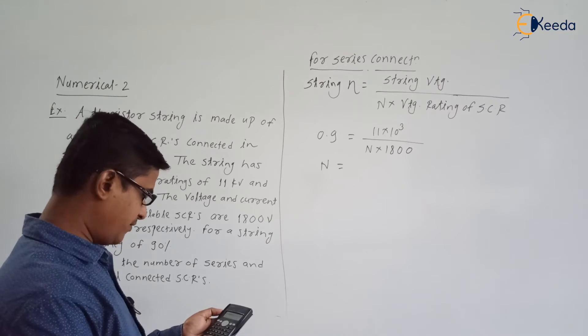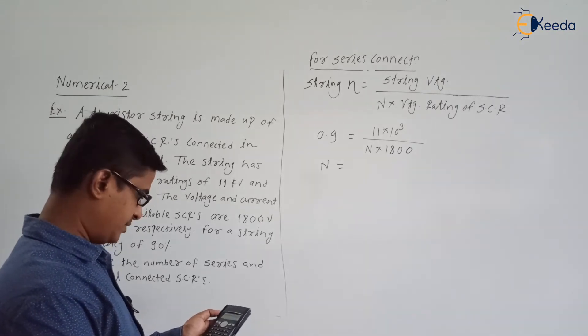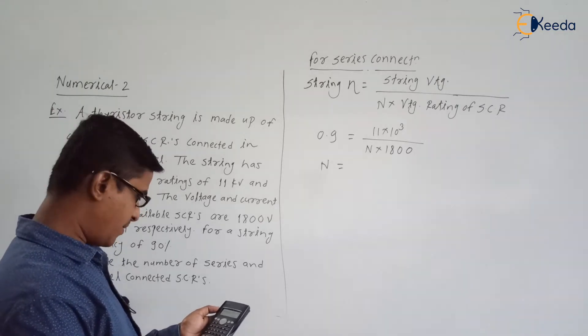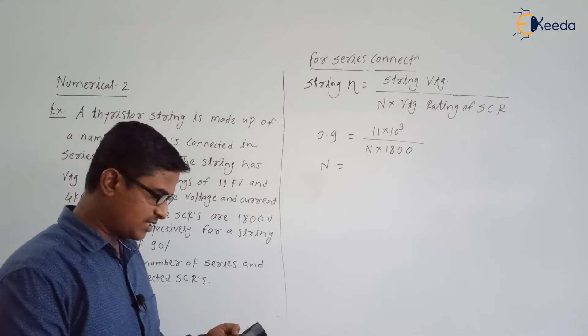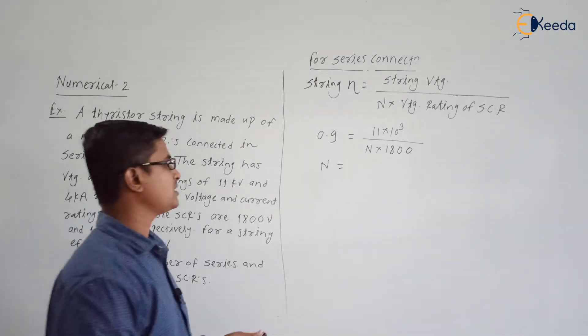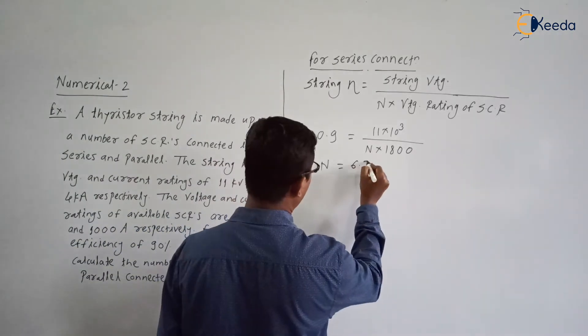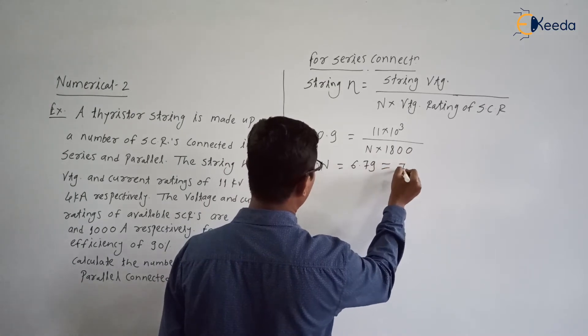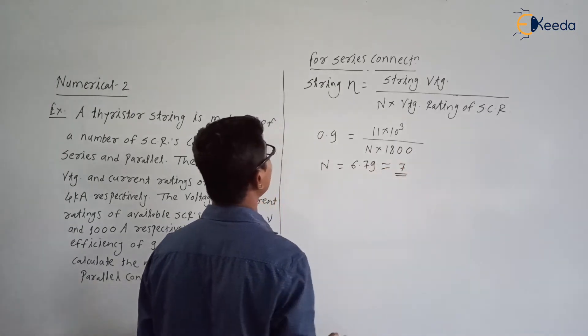So from this can we find the number of SCRs required to be connected in series? Yes, we can find. 11 kV divided by 1800 divided by 0.9. So it is 6.79, so it is 7. So 7 SCRs we need to connect in series.